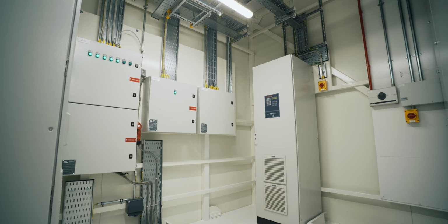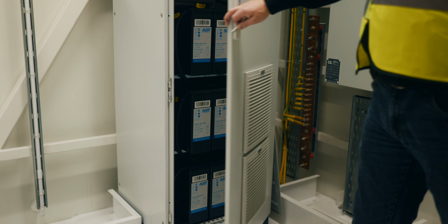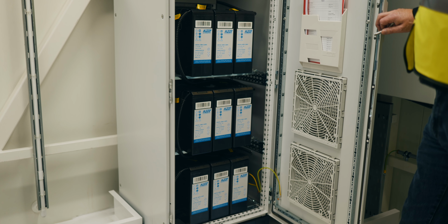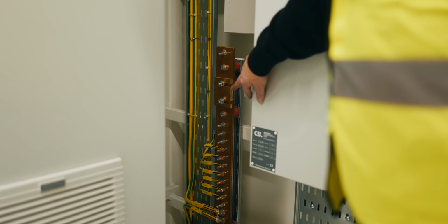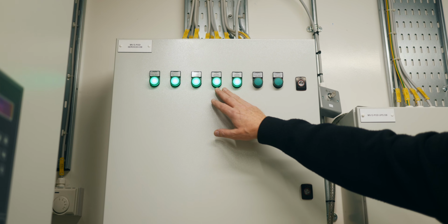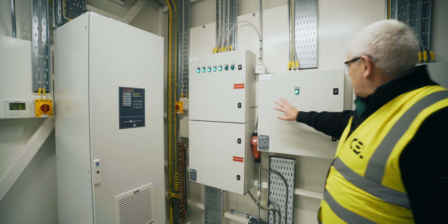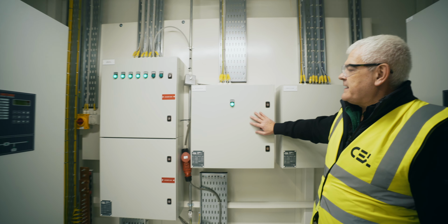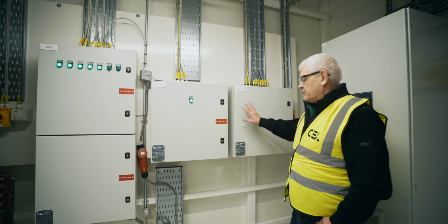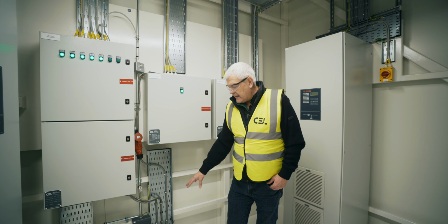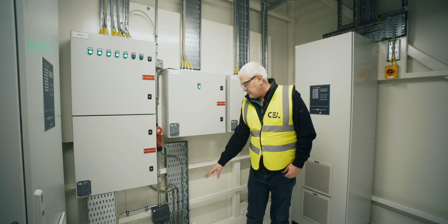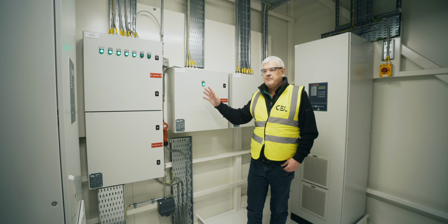The MV pod has battery tripping units, 110 volt DC supply to our breakers within the ABB Unigear. We also have our own internal earthing system and house distribution board. And then it also has a UPS backed distribution board and a remote I/O panel. These are all set, ready for cable entry. Once it arrives at site, the whole system is ready to be powered up.